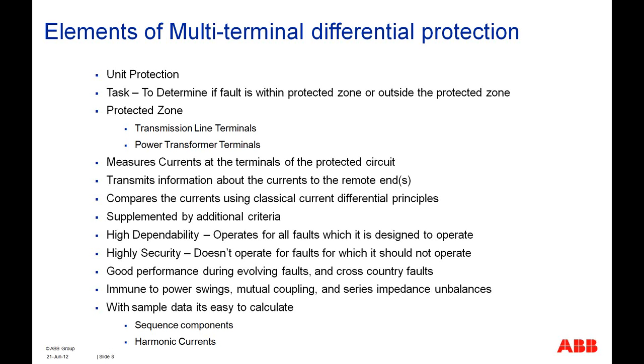What it essentially does is measure the currents at the terminals of the protected circuit, and then transmit the information about the currents to the remote ends. If it is two line ends, then we have one remote end. If it is more than two, up to five line ends, our ABB line protection can handle it, so we'll have four other remote ends. And it also compares the currents using the classical differential protection principle. And then, of course, we have to supplement that current differential principle with some additional criteria to cater to specific needs.